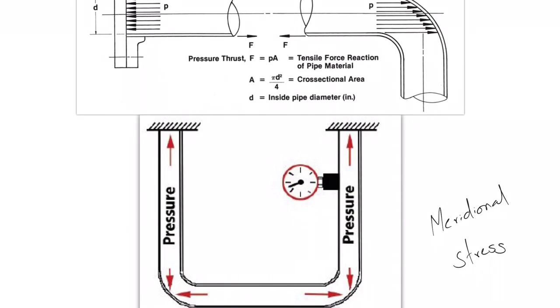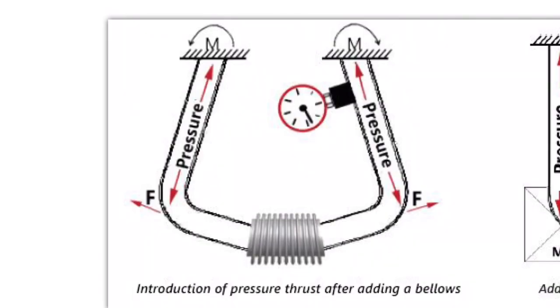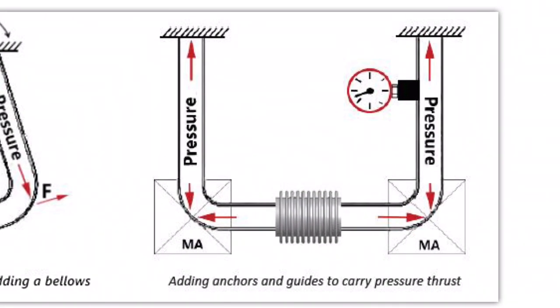As you can see, I have introduced an unrestrained expansion joint. The key important concept is that this is equivalent to cutting the pipe because of the inherent flexibility. It makes it unable to transmit the force as in the earlier case. This will lead to large deformations and even bellow failure. How can we prevent it? Easy—we need to provide supports or anchors as shown here.